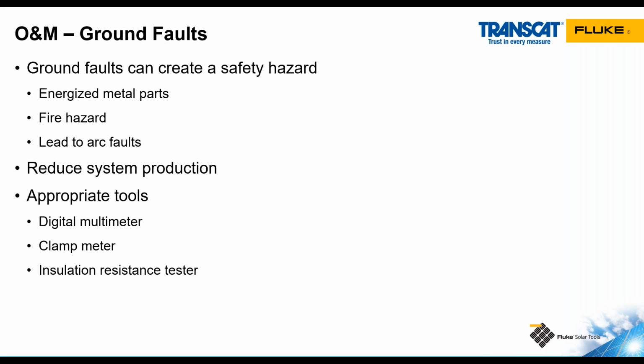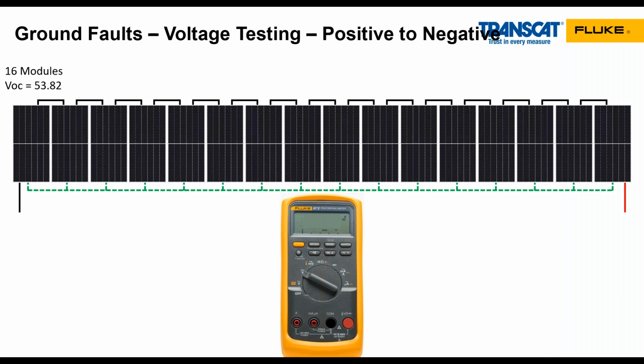You can use any kind of multimeter, clamp meter, or insulation resistance tester as long as it's properly rated for the environment and the voltage that I'm working on. So let's look at some examples of how we can use voltage testing to find a ground fault in a PV source circuit of modules.